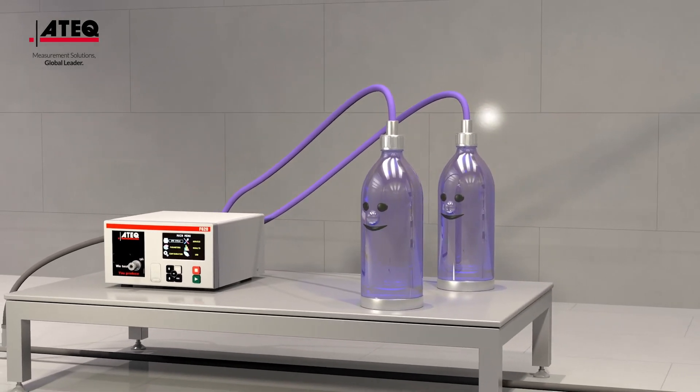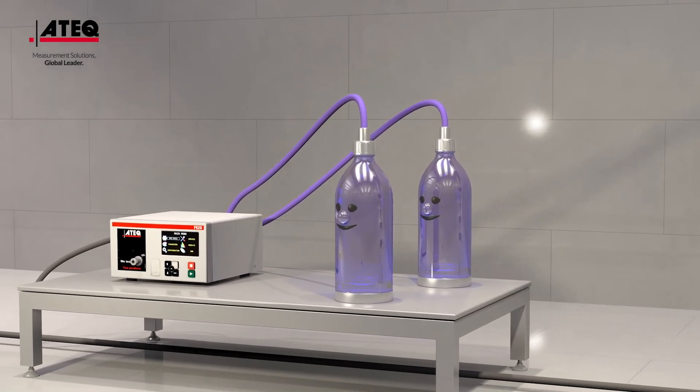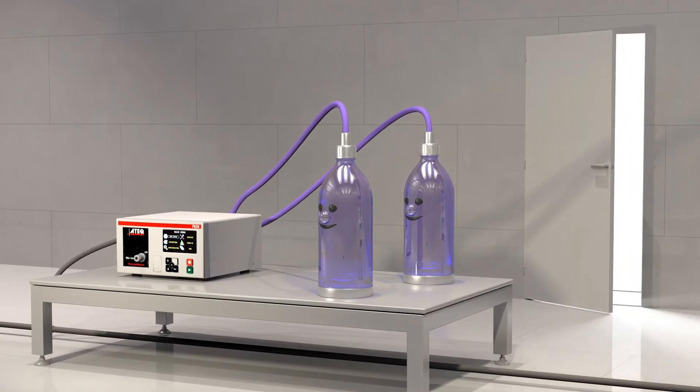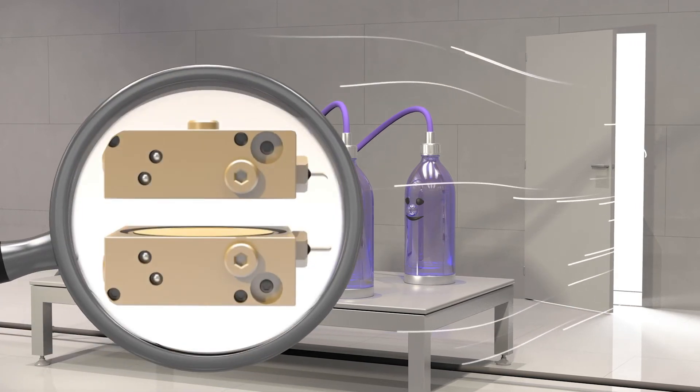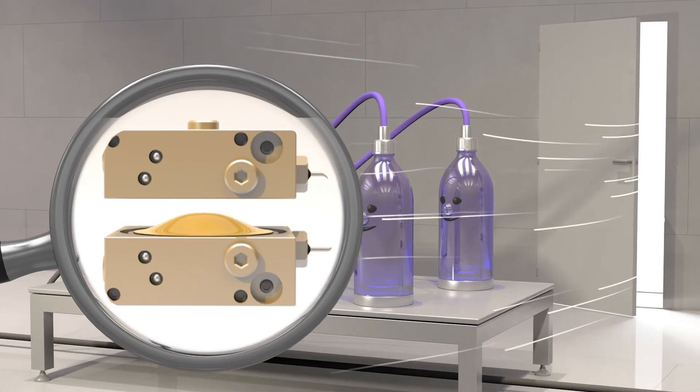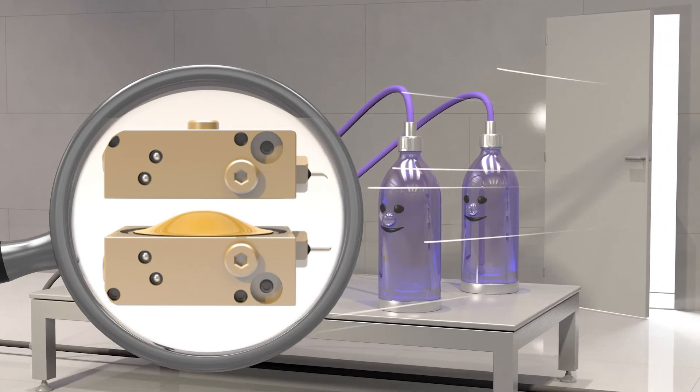But the differential pressure drop has another benefit. When ambient disturbances, such as air currents, occur, the differential pressure test is not affected. The micropressure variations won't occur on the two pieces at the same time and in the same proportions. Only a leak will create a difference and will be detected.